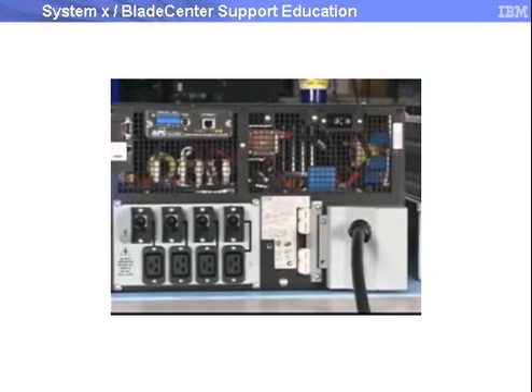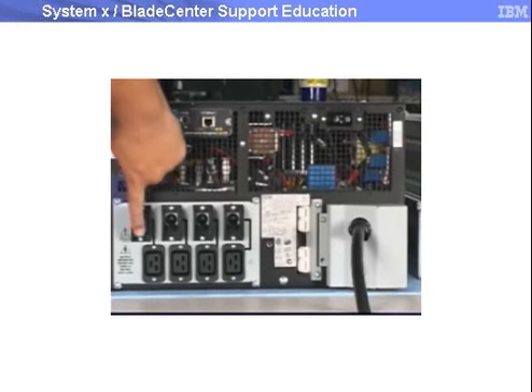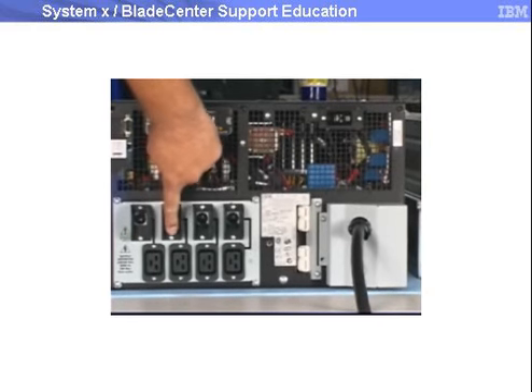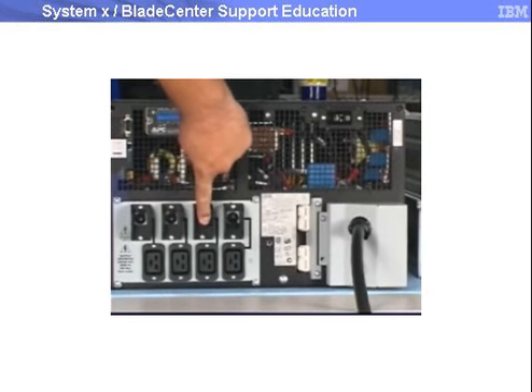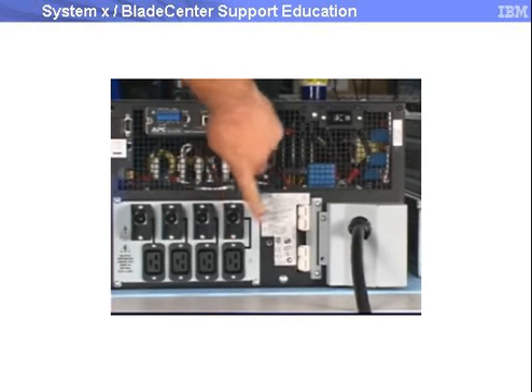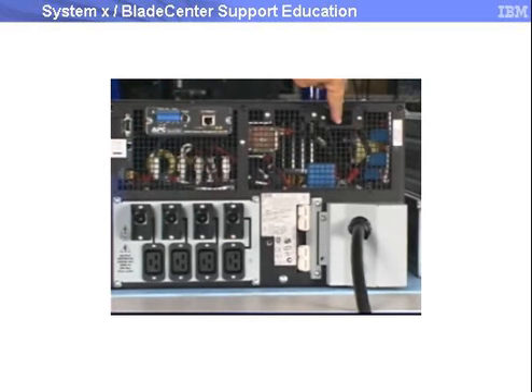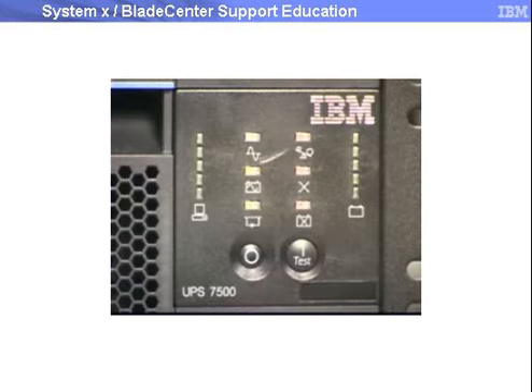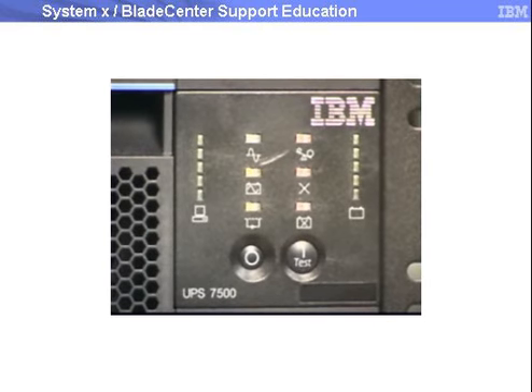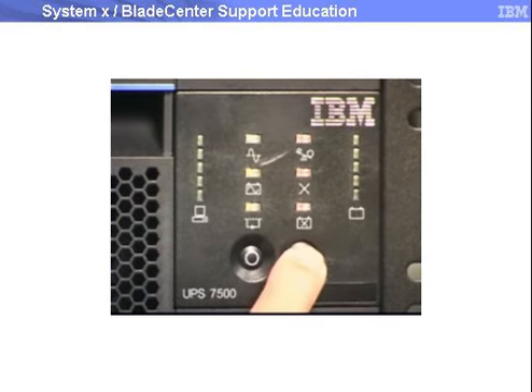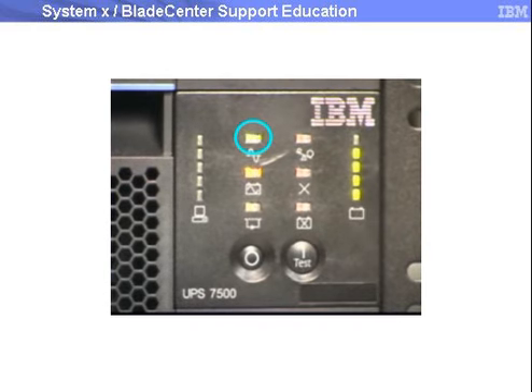Switch the external distribution panel circuit breaker on, and then the UPS power supply circuit breakers and utility circuit breakers to on, and check the line voltages. Press the on button on the UPS front panel to turn the UPS on. The online LED will begin flashing, indicating the unit is executing its self-test. When the online LED stops flashing, self-test is complete.